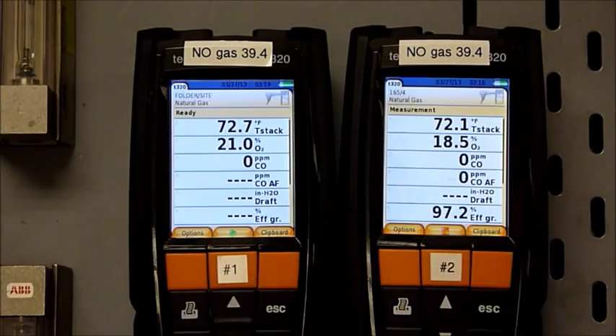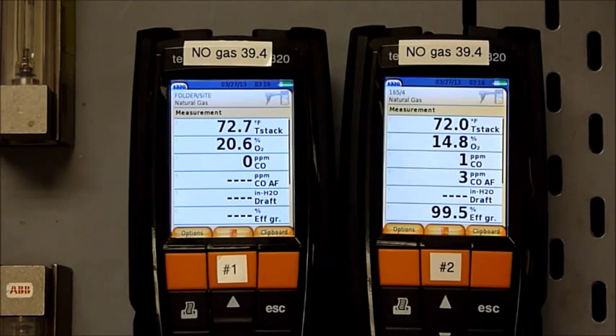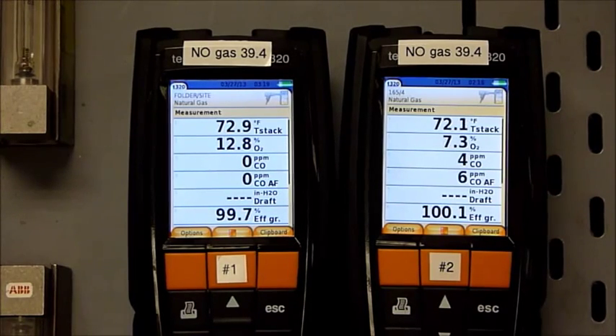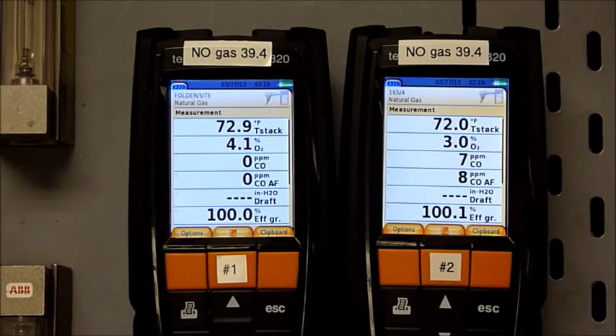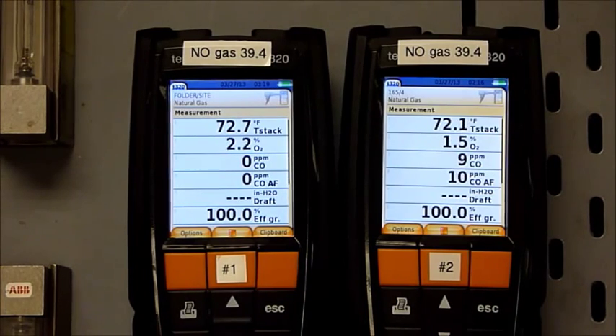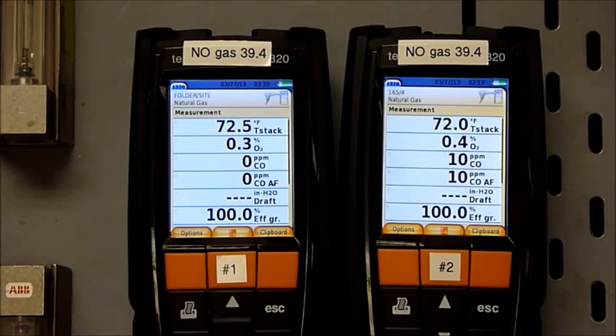We'll start both analyzers, and what you'll see is the oxygen coming down, and we immediately see a CO reading on the sensor that does not have the NOx filter. The one that does have the NOx filter is reading correctly. There is no CO in this calibration gas. What this demonstrates is that if you're using an analyzer that doesn't have a NOx filter, or has a depleted NOx filter, you can be measuring CO at the wrong concentrations.